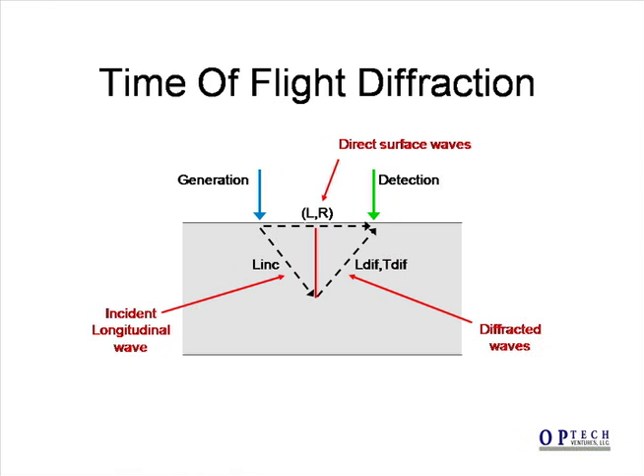For measuring the crack depth, we use the familiar time-of-flight diffraction technique, in which we detect a wave that travels to the crack tip and then diffracts up to the surface on the opposite side of the crack. The time-of-flight and wave velocity can be used to determine the propagation distance, and the crack depth is determined from this value and the known beam separation on the surface.